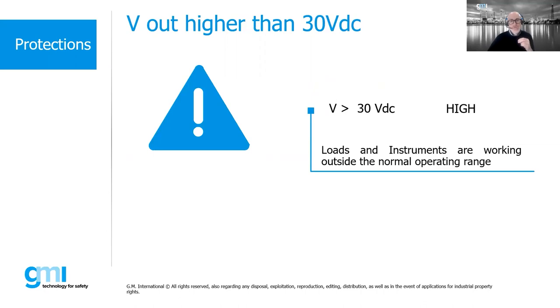The second dangerous failure condition of a power supply is when the output voltage reaches a value higher than 30 volt DC. In this condition, the load is subjected to an extra voltage, which can damage it. Or in case of output voltage higher than 35 volt, the field instrumentation can suffer a definite disruption.